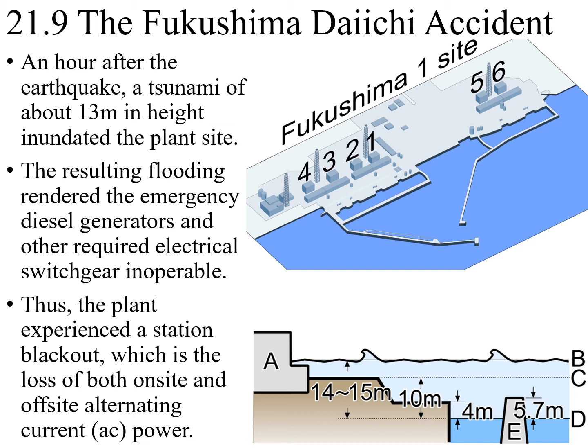The resulting flooding rendered the emergency diesel generator and other required electrical switchgear inoperable, because the diesel generator was located in the basement. So this is not a good design. Thus, the plant experienced a station blackout, which is the loss of both on-site and off-site power. At this point, only the Unit 3 DC batteries were supplying its instrumentation and control systems, but sufficient power was not available for large equipment such as pumps.